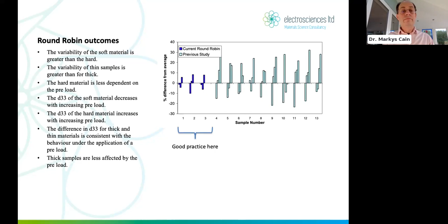Quartz is a standard that's used across the world in any piezoelectric measurements, whether it be direct or indirect, whether you measure the displacement with applied voltage using interferometry, or a resonance method, dielectric resonance method, or using a Berlincourt type method like we're describing here. And you might ask yourself, how do I calibrate the response of my system, the PM300 system, using quartz, where the d33 is only 2.27. It's very, very low d33.